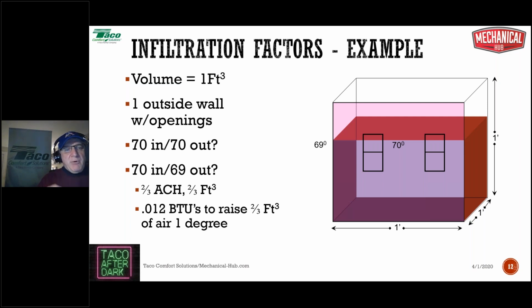I'm going to need 0.012 BTUs to raise that 2/3 of a cubic foot of air 1 degree. All right, that's what those factors mean, that's where they come from. They're BTUs needed to raise a certain amount of cubic feet of air 1 degree Fahrenheit in 1 hour. So that's why we're going to use 0.012, and that's what the number means.